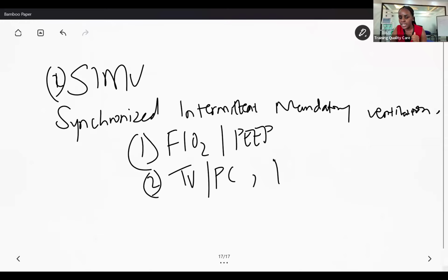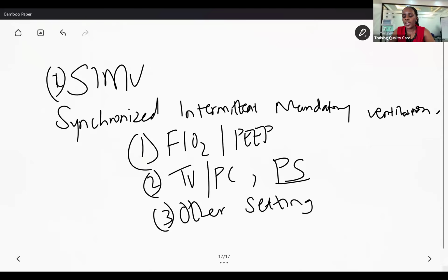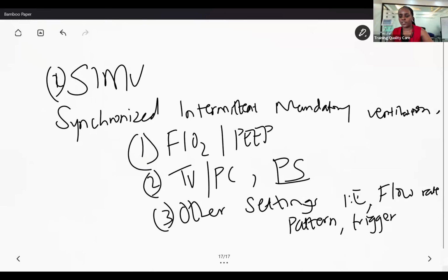And in this one, we are also going to set the pressure support. Pressure support is for when the patient decides to initiate their own breath. The ventilator will not give the mandatory breath, but it will allow the patient to have a spontaneous breath. Because the patient might not be able to have an adequate breath, you set some pressure support in addition for the spontaneous breath. Then we set the other settings: the IE ratio, depending on your patient, your flow rate or pattern, your trigger, all that. That is synchronized intermittent mandatory ventilation.